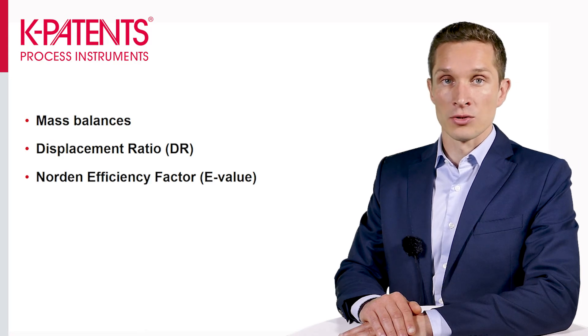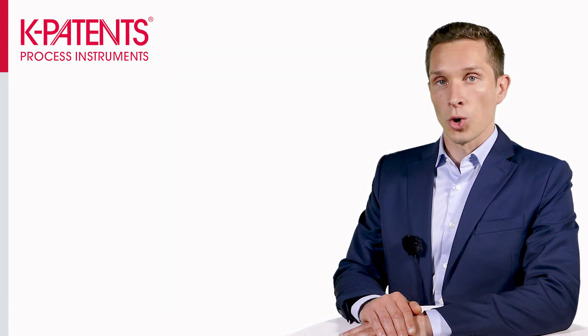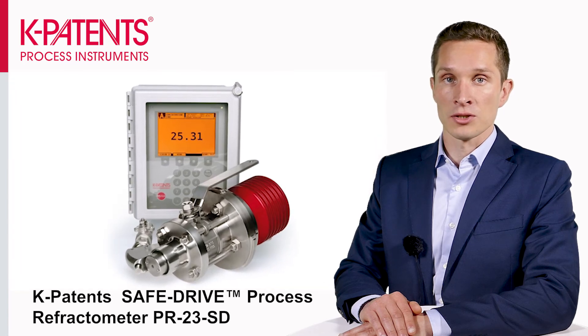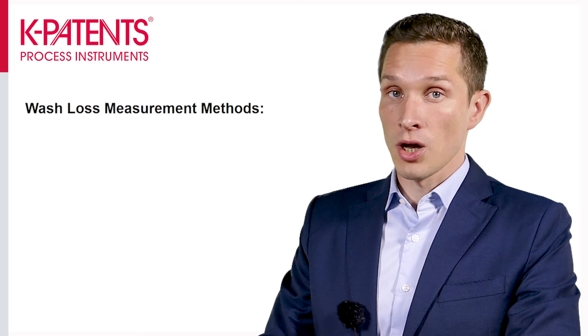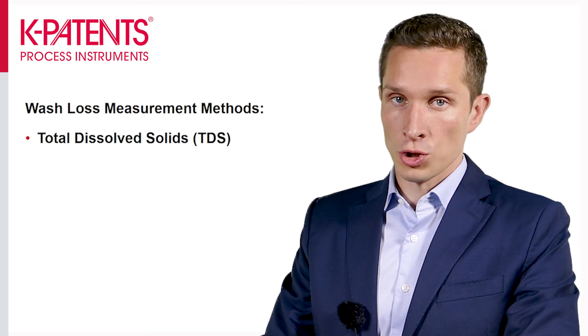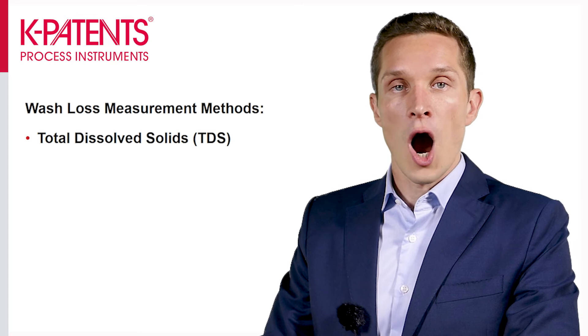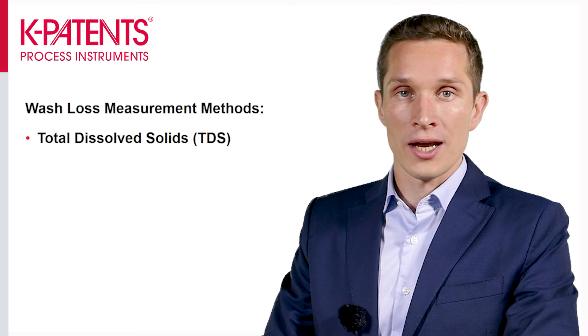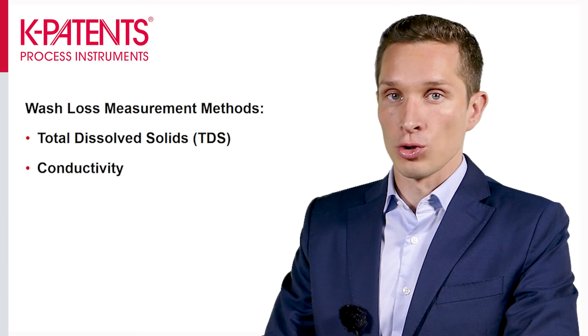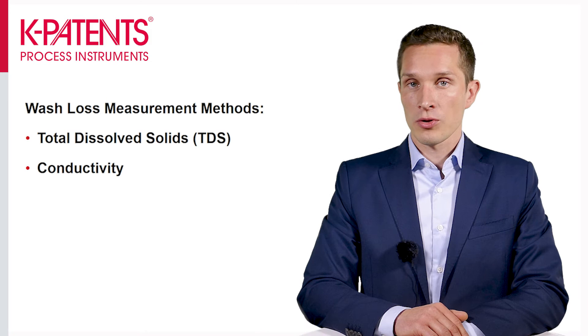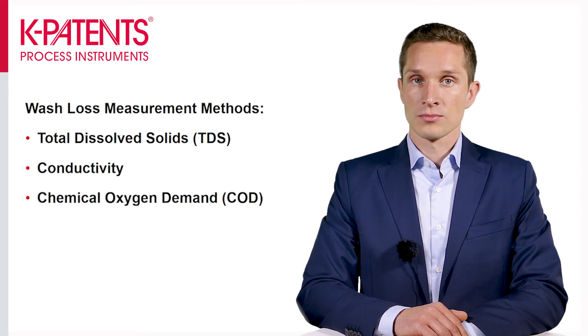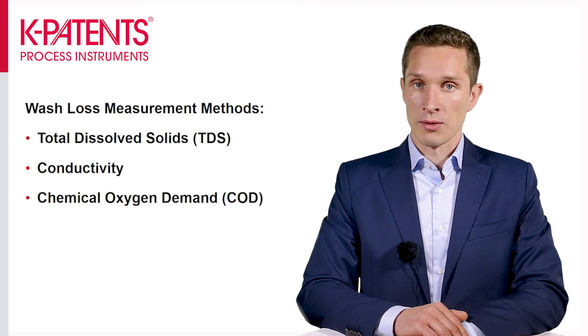Other important parameters include mass balances, displacement ratio, and the Norden efficiency factor. These indicate the true washing efficiency and even help to further enhance it. The wash loss as well as these important parameters can be obtained in real time by using K-Patents inline solids measurements. Dissolved solids have always been used to measure wash loss and washing efficiency. However, it has not been possible to measure dissolved solids inline, and therefore the inorganic changes by conductivity have been used as a real-time wash loss indication. Another common method to indicate wash loss has been chemical oxygen demand, COD, as it correlates with bleaching chemical consumption.